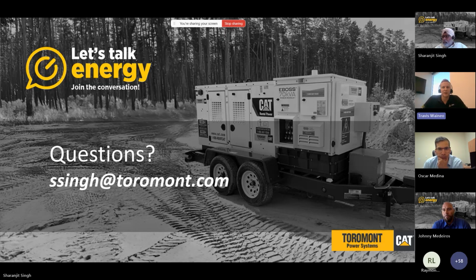Yeah, that's a great question. From the EBOSS hybrid system we've got here, we really don't have a limitation on how many paralleled systems we can put together. We use a simple droop-based frequency load sharing. So if you need a 5 megawatt system, you just pile as many of these systems into that power node as you need. We've got applications where there's 40, 50, 60 of these paralleled together to build up that larger power node. The really interesting part that Johnny and Oscar would probably appreciate is you can build these systems up into a large power node, say 100 of these 70 kVA units to build a 7 megawatt system.